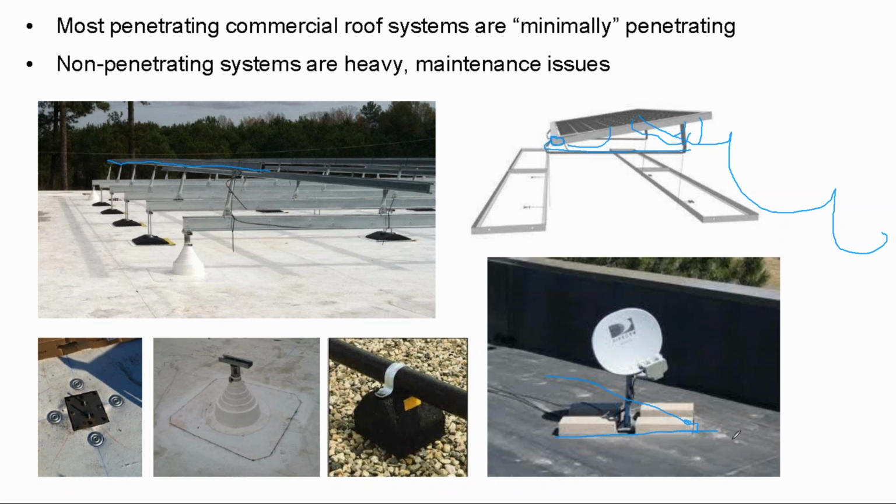Now, I've seen commercial rooftops that are flat, and when it rains, over an inch of water accumulates on the rooftop. I've seen commercial rooftops where the drains have levees built around them so that the entire roof water cannot make it to the drain, more or less. And so putting the solar modules just inches from the surface of a rooftop might be fine in sunny California or the desert where it doesn't rain all the time.